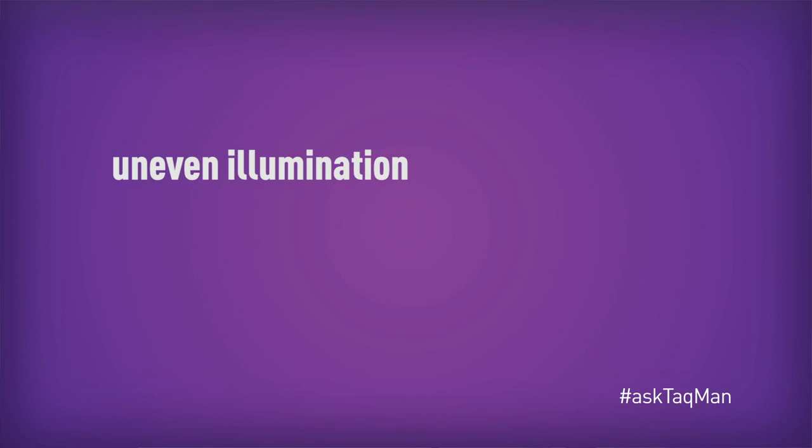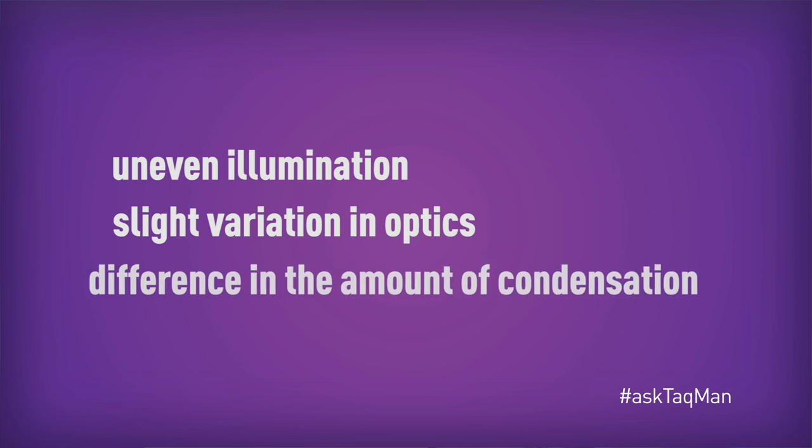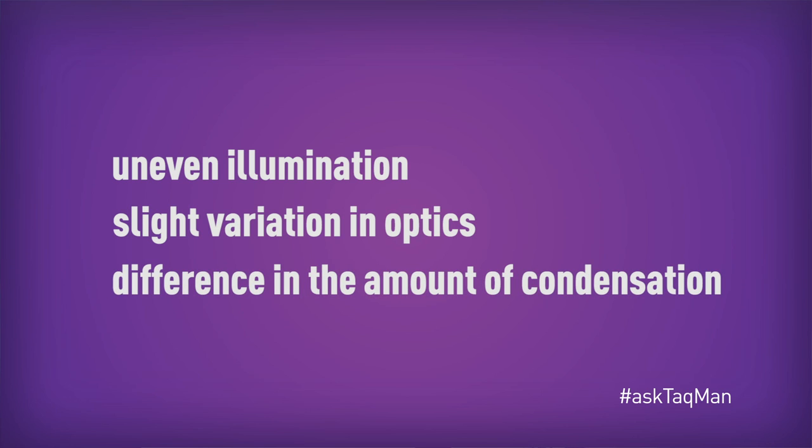Instead, ROX just sits there. Within any real-time PCR system, there are several potential sources of well-to-well variability in the excitation of the reporter molecule, and therefore in the detection of signal from the reporter. These include uneven illumination, slight variations in the optics from well-to-well, and even differences in the amount of condensation.